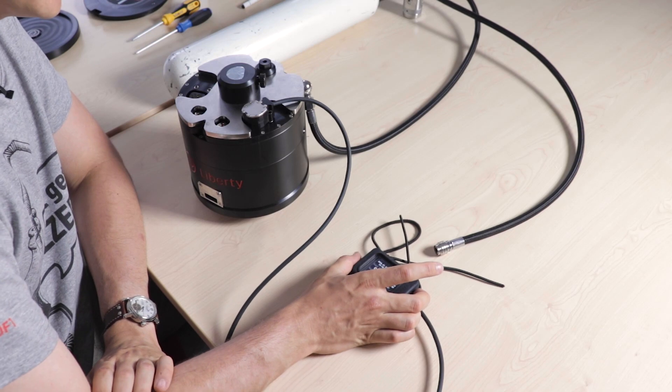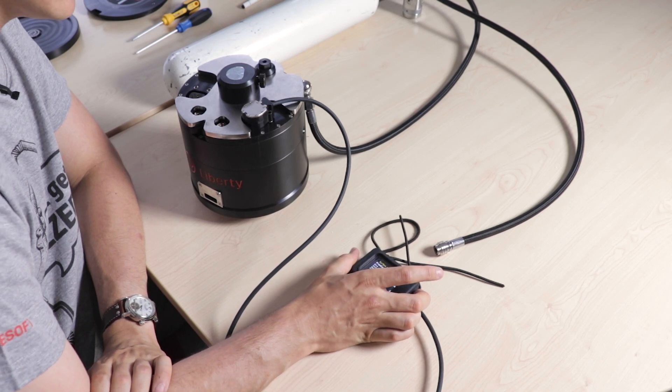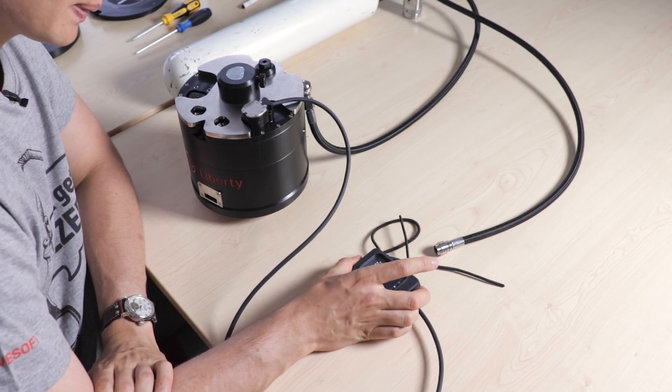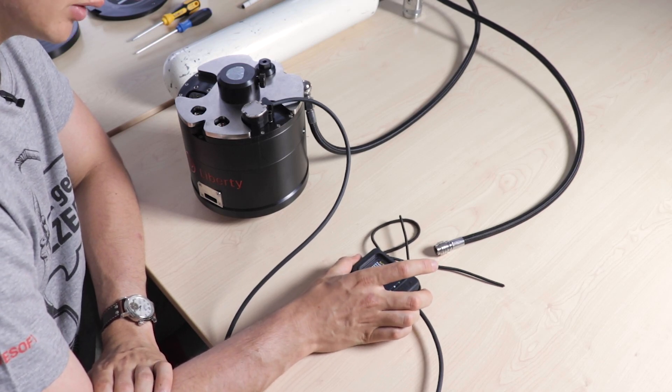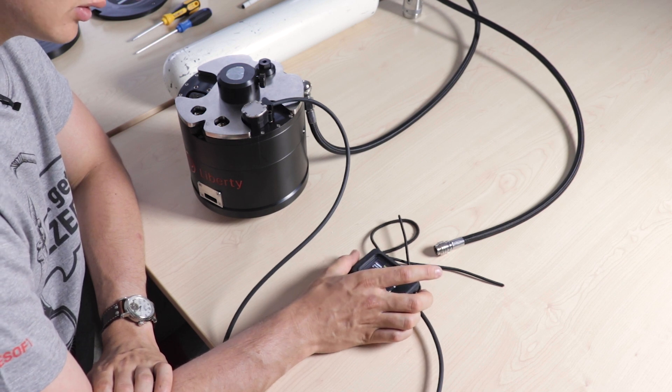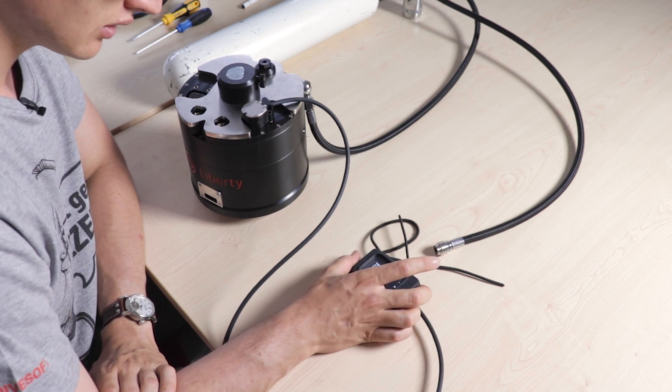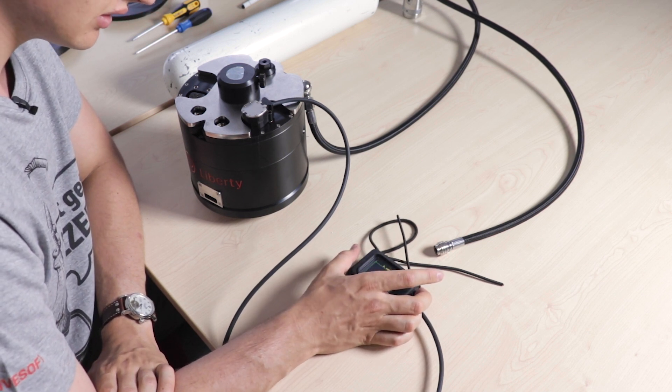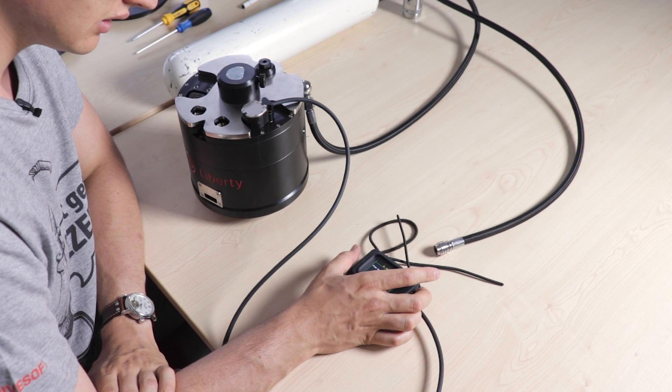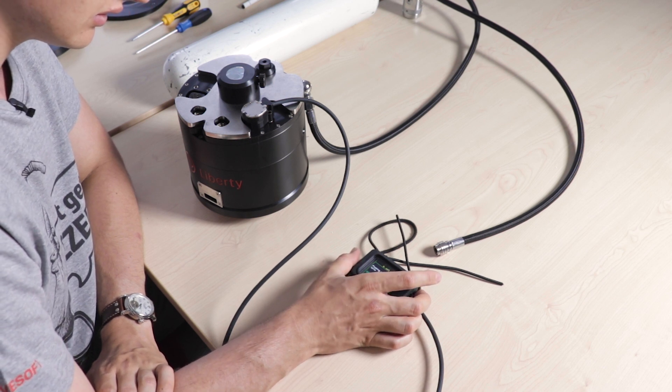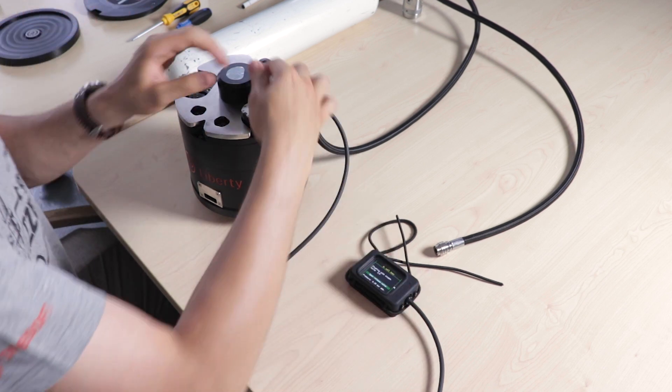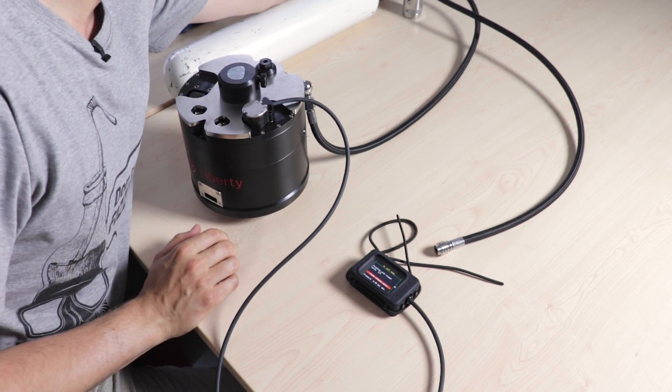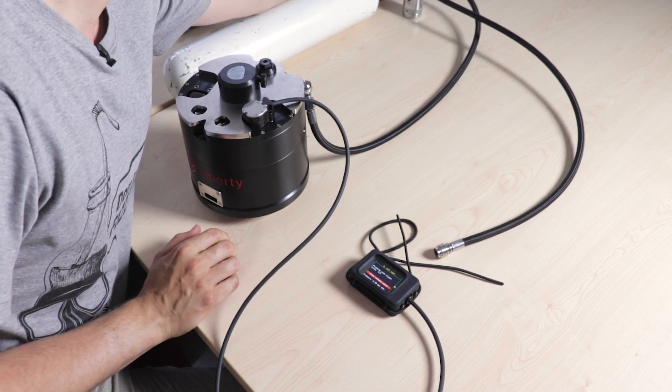Now you go to the main menu, go to applications, O2 cell test, and you open the release valve. Now you flush it with oxygen.